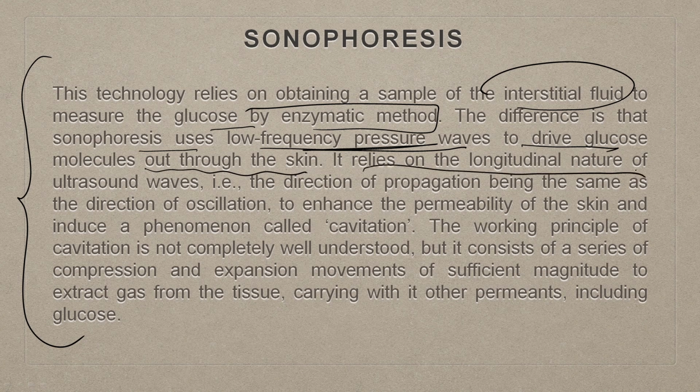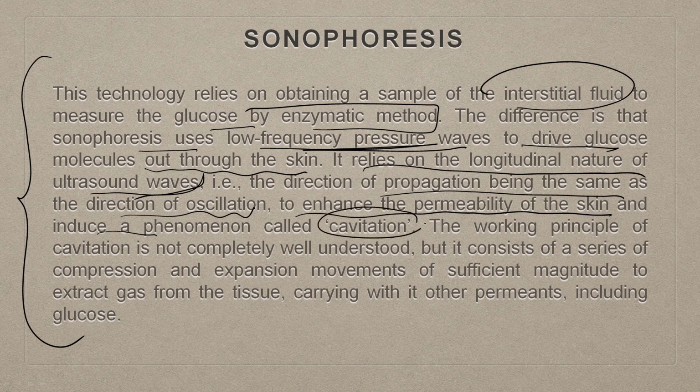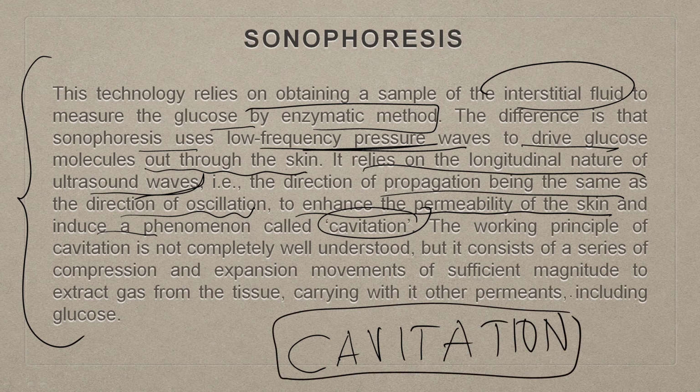It relies on the longitudinal nature of ultrasound waves, the direction of propagation being the same as the direction of oscillation, to enhance the permeability of the skin and induce a phenomenon called cavitation. Okay. The working principle of cavitation is not completely well understood, but it consists of a series of compression and expansion movements of sufficient magnitude to extract gas from the tissue, carrying with it other permeants including glucose.